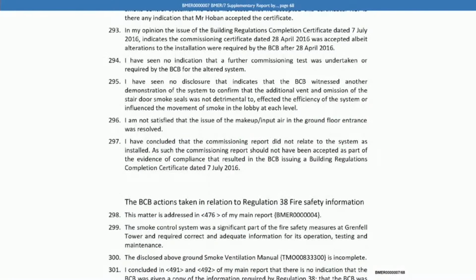Moving on to a topic you've already mentioned, the make-up air and the additional vent proposed by Mr. Hansen. If we go to your report at page 68, paragraphs 296 and 297, you say you are not satisfied that the issue of make-up or input air in the ground floor entrance was resolved, and you conclude that the commissioning report did not relate to the system as installed, and as such the commissioning report should not have been accepted as part of the evidence of compliance that resulted in the BCB issuing a building regulations completion certificate, and you give the date there.